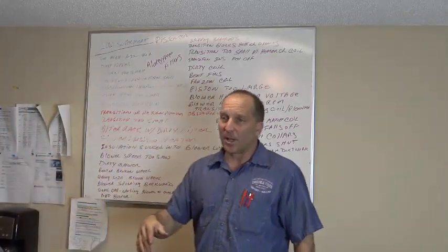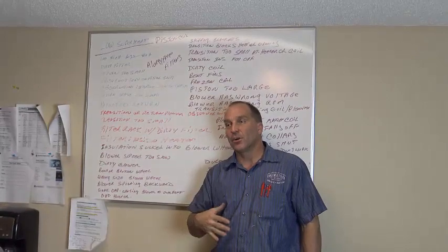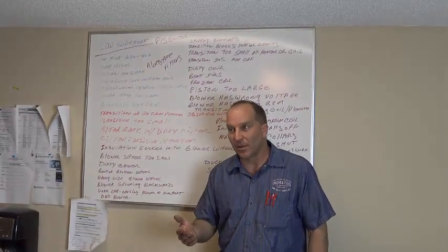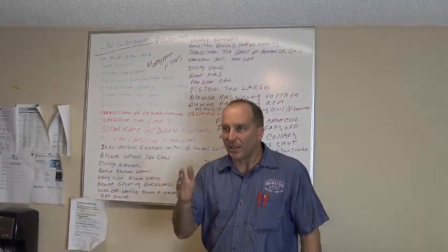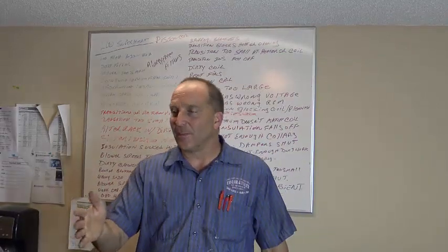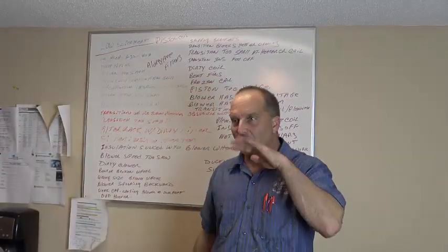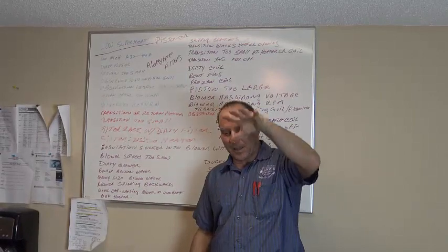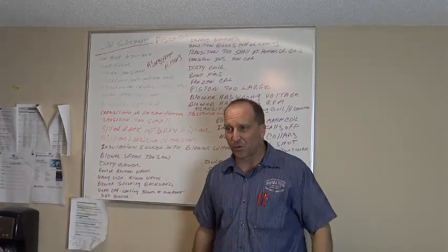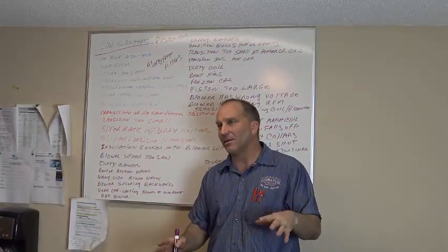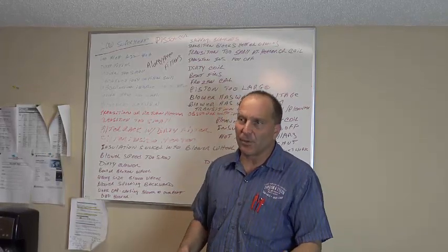A lot of times when I put a unit underneath the house years ago, when it was still code that you could do that, I would always leave that filter inside that heater, because if it's underneath the house, there's a return grill on your floor, and that return plenum gets full of trash and dirt and dog hair and all that kind of stuff, and they're never going to change their filters there.